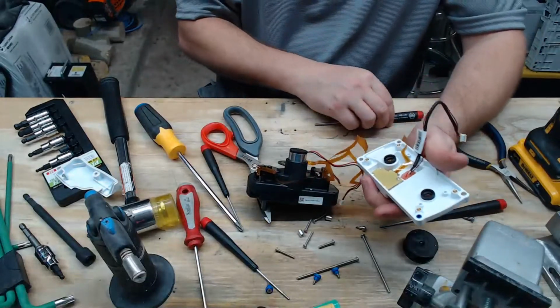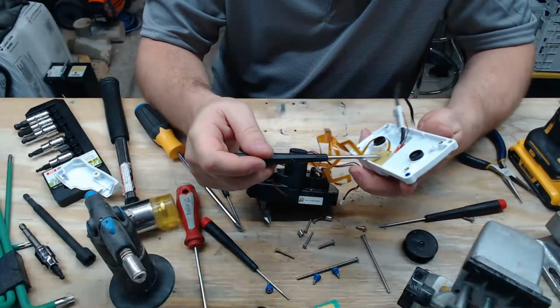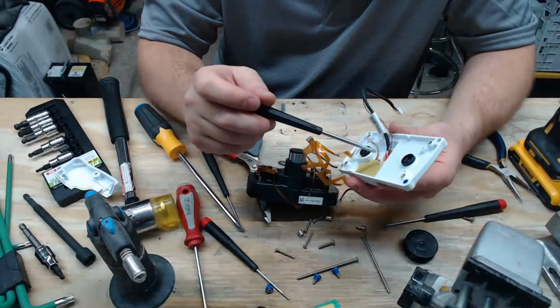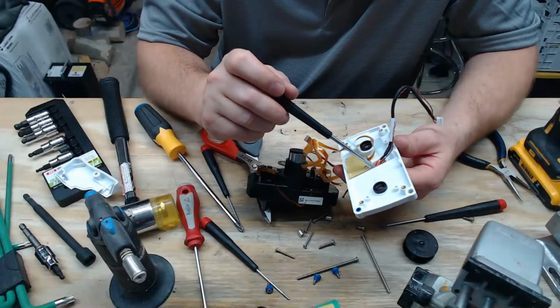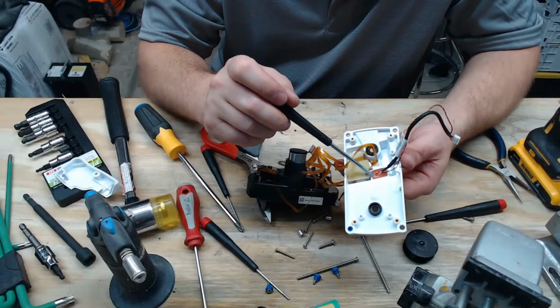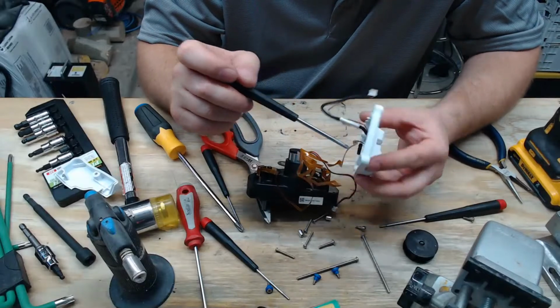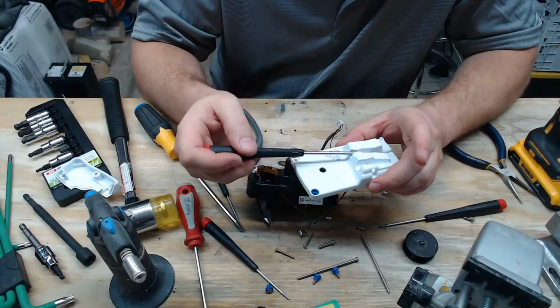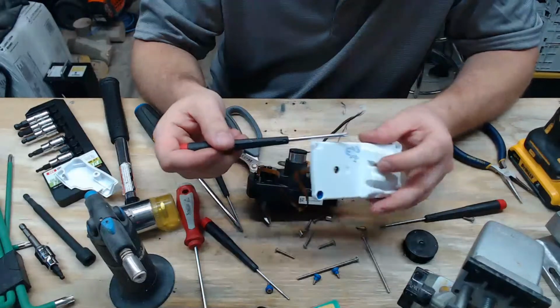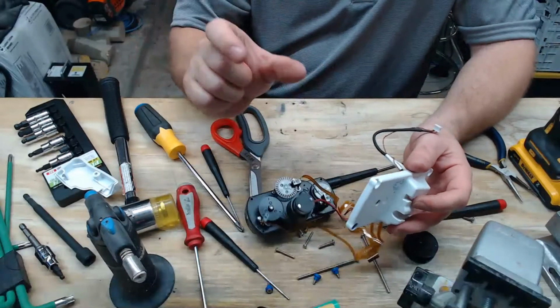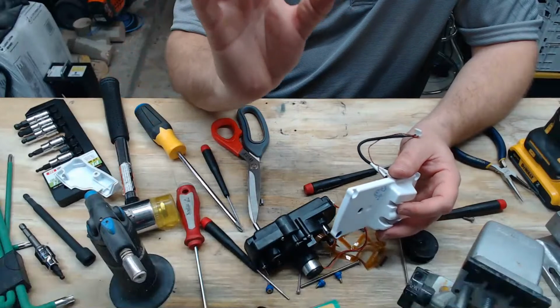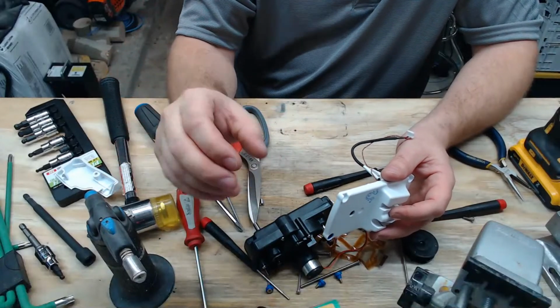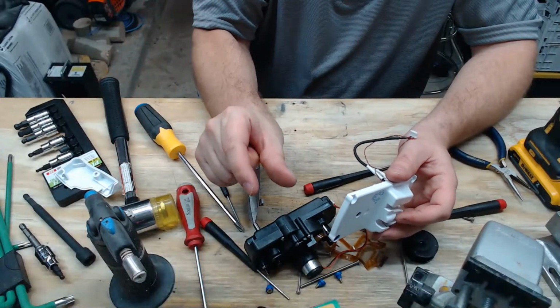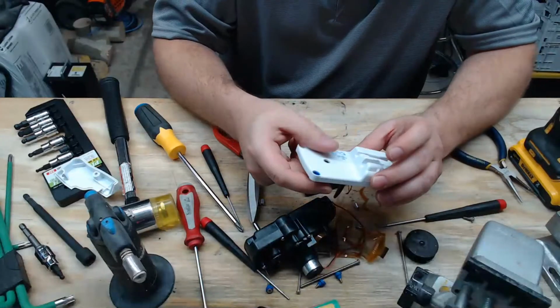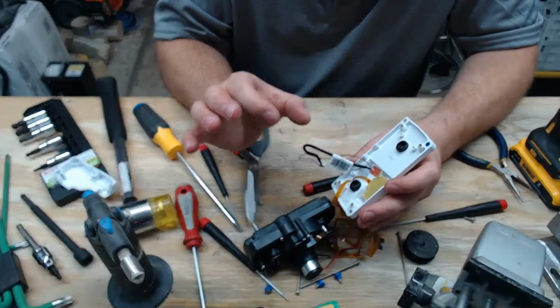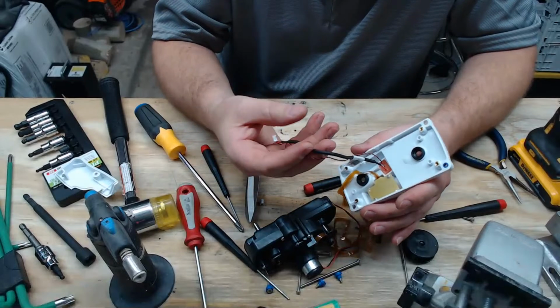So it detects when your fluid is out, and it also detects when the set is loaded. I'm guessing that this one over here, that's epoxied in, is the ultrasonic. You can tell it goes through a little cavity right here. Anytime you have an ultrasonic sensor, it's going to be in a spot where the tubing is kept really close and kind of pinched in there, because it's got to have very close proximity to get a good reading.